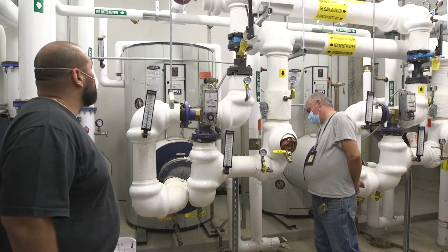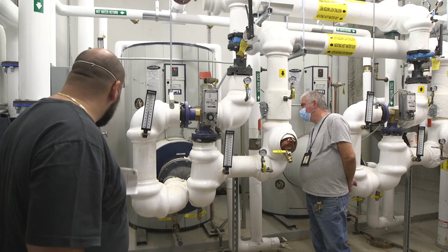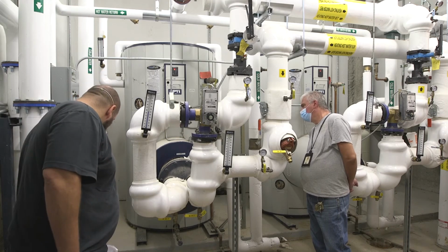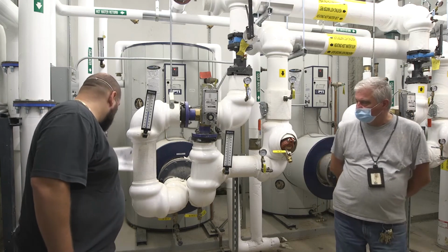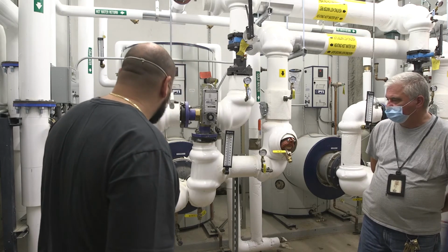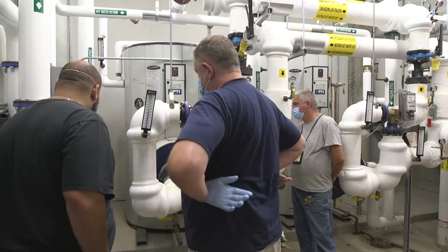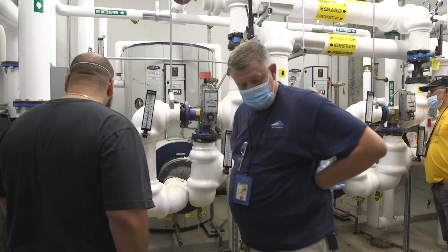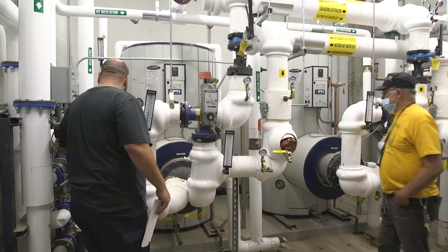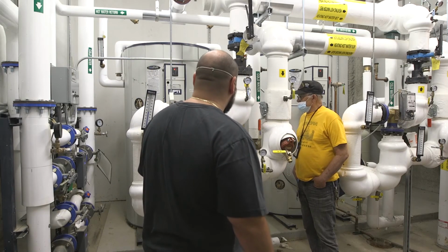On this one, on the upper one, you see the butterfly valve is over there. It's not fully open on the top one. Yeah, that one? Yeah, you should fully open that. No, the butterfly, the hand one. That one over there. No, here, right here, the first one. Can you point it out? Yeah, it should be open fully. This one.